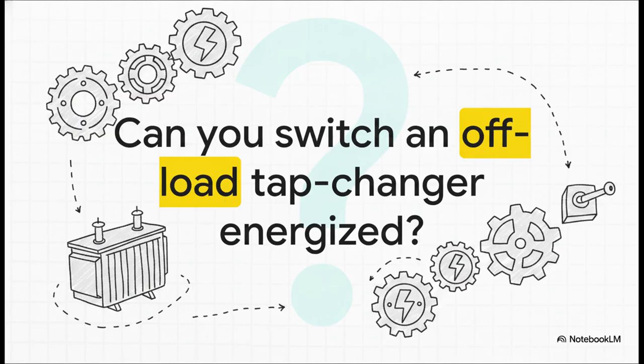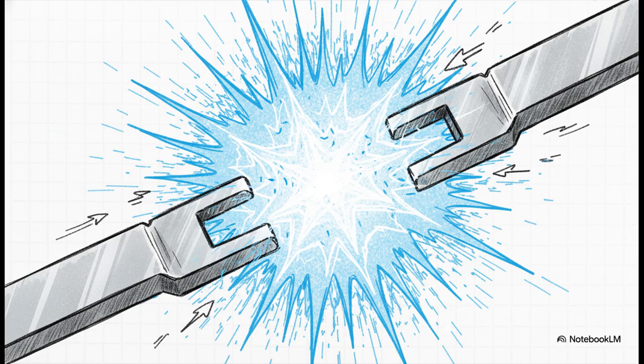Here is a critical safety question for you. Can you safely operate an off-load tap changer while the transformer is actually energized and pushing a load? Take a second and really think about that one. The answer is an absolute definitive no. Seriously, do not do it. Off-load tap changers physically reconnect the winding taps. If you try to switch gears while that system is energized, you're going to draw a massive, incredibly violent electrical arc. It'll instantly cause severe contact damage, or honestly, much worse.